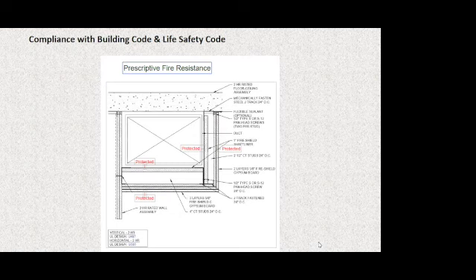And we can see it takes an extra layer of drywall on the horizontal part versus the vertical part to get to that same 2 hours. Horizontal is harder. It's not just harder with drywall fire-rated assemblies, it's also harder for fire-rated duct assemblies when we start moving through the building horizontally versus vertically. We need to pay attention to that because we have to use it the way it was tested, right? How many times have you seen a drywall assembly where they took the vertical wall design and just brought it down and turned it and ran underneath the duct horizontally? They didn't even do the horizontal up build that is minimally required. They took a wall design that was tested vertically and they turned it horizontally. It's not going to work.